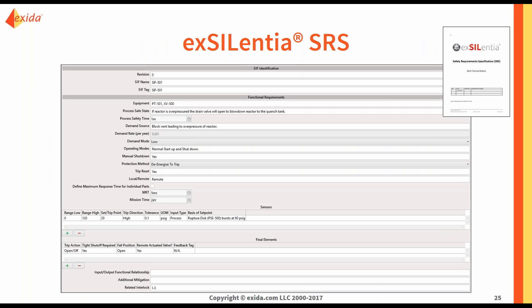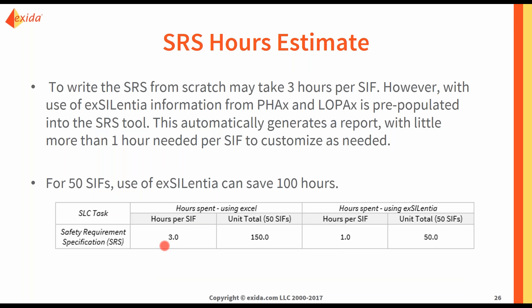Once SIL selection is complete, you move on to the safety requirements specification. This document outlines the purpose and target SIL of each SIF, answering: what is the safe state, what equipment needs to be protected, what actions must be taken, and what is the response time. It summarizes findings from the entire analysis phase and becomes the guideline for design and implementation. In ExSILentia's SRS module, much of this information is pre-populated from your LOPA and PHA — calculated demand rates, tag names, and more. Writing the SRS from scratch takes 3 hours per SIF, but with ExSILentia it takes only 1 hour, saving 100 hours over 50 SIFs.